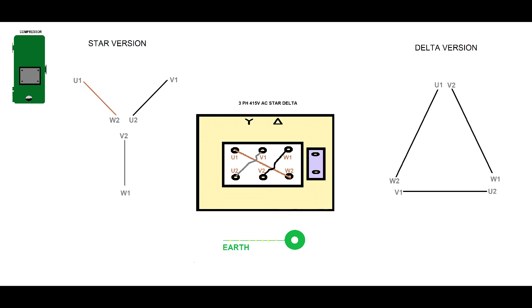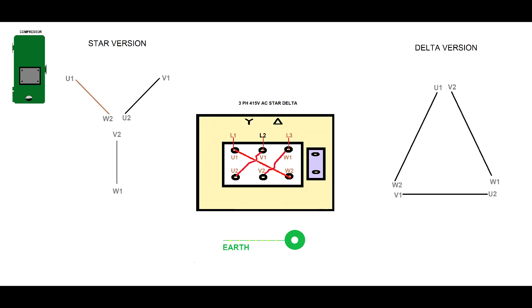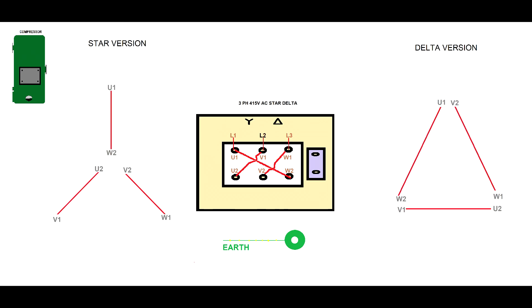This type of compressor winding comes not configured at all — you have three individual windings. If you apply power to only three terminals, nothing will happen; you only bring three-phase power into three individual windings. As you will see, the three phases will not meet at any point — three windings will have a 415 V potential between themselves — so the compressor will not run. Let's turn the electricity off and start again.